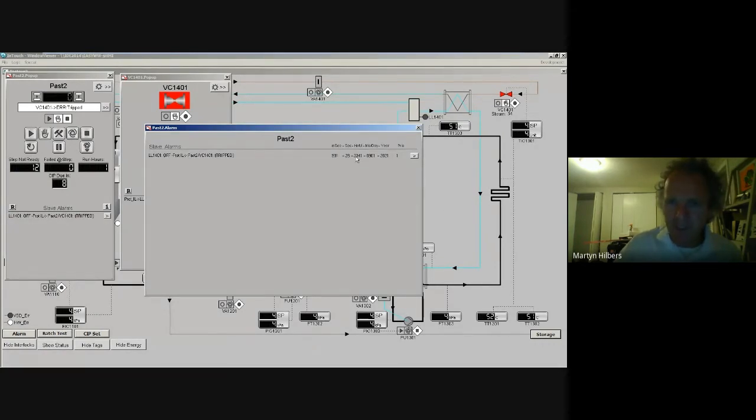Now you can see here it's at 11:41. And if I'm looking at my SCADA clock, you see here on my SCADA, it is the 2nd of September at 5 o'clock. And so you can clearly see this timestamp does not originate from the SCADA. It originates straight away out of my PLC.